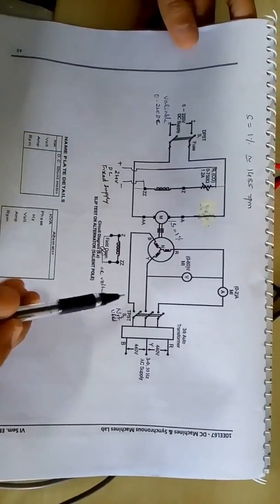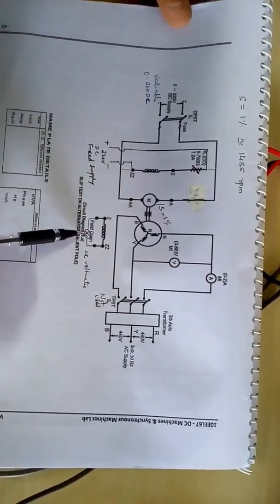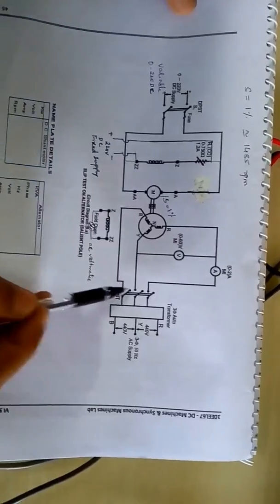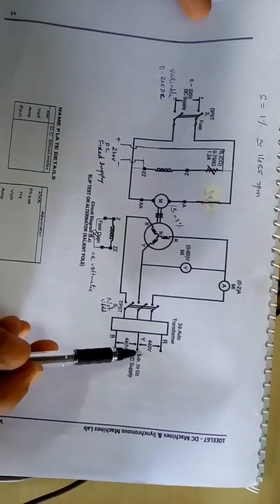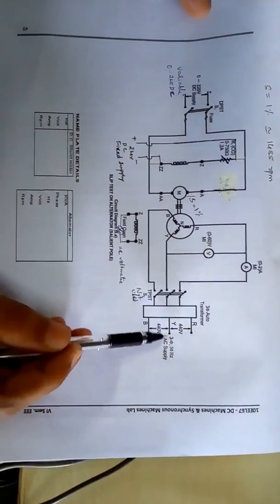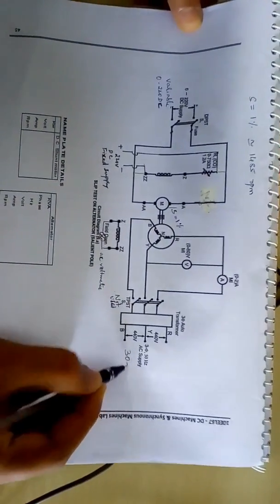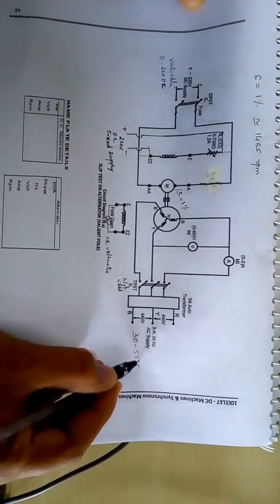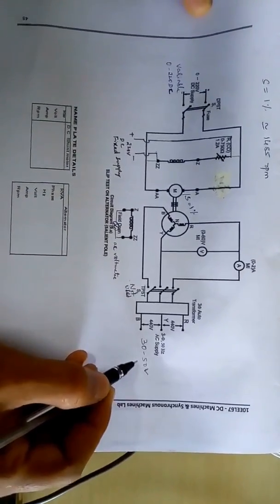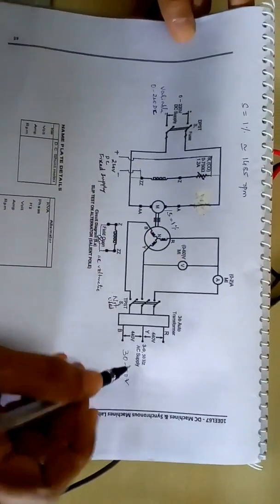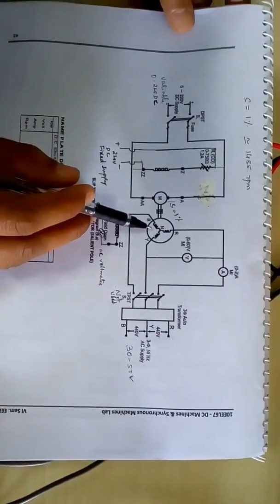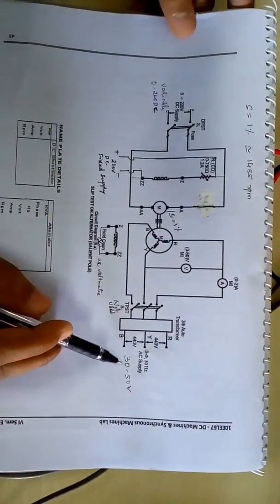Once you make sure that this reading is less than 12 volts, you give the stator supply through auto transformer around 30 to 50 volts. It should not be rated voltage.